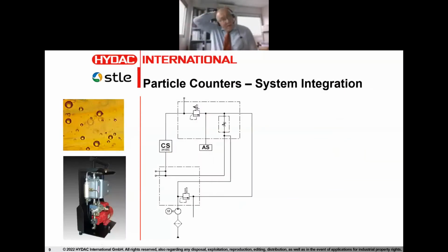The drawback of it is that the light obscuration is obviously going to be subject to a decrease in light intensity, which can result from various mechanisms. So anything that either scatters, refracts, reflects, or absorbs light is going to be counted as a particle, because the particle counter just simply doesn't know. So any water bubbles, even silicone antifoaming bubbles, because silicone antifoamants are typically prepared in fine dispersion within the oil, will get counted. The silicone droplets will get counted as particles. Air bubbles will get counted as particles.